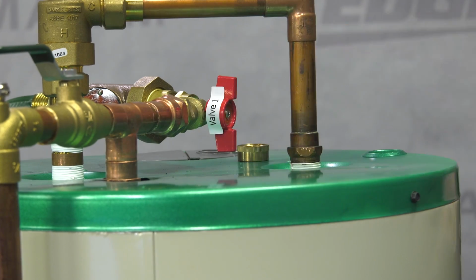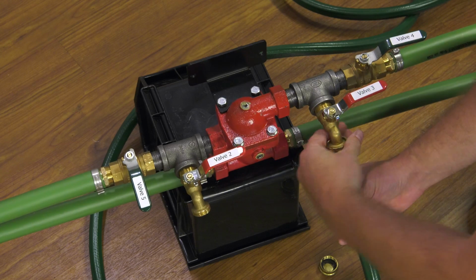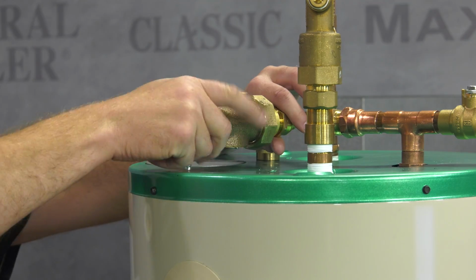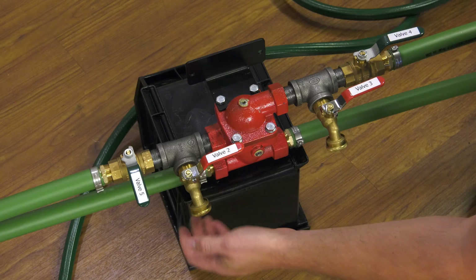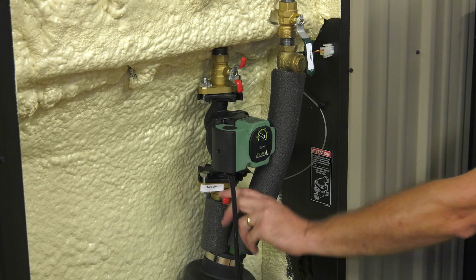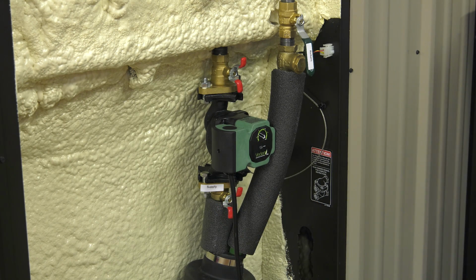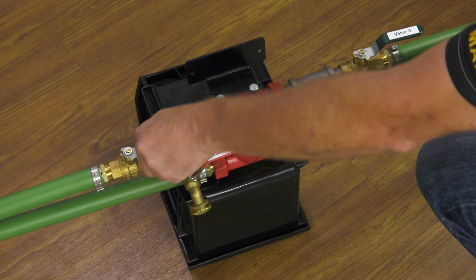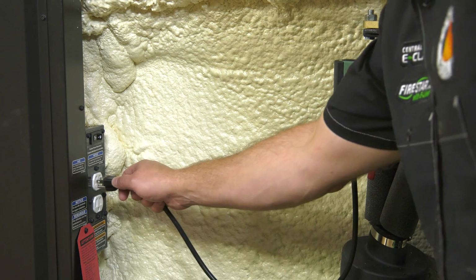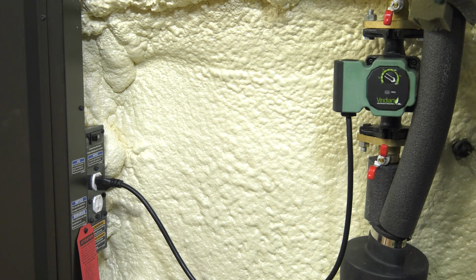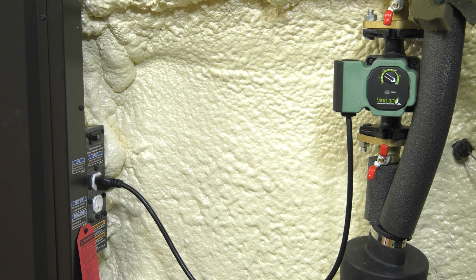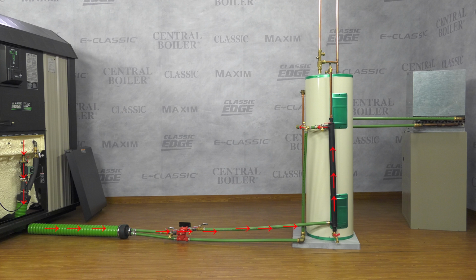Close valves 1 and 3, disconnect the garden hose and the backflow preventer and replace the caps on valves 1, 2, and 3. Open the valve on the hot supply line of the outdoor furnace and valve 5. Start and run the pump or pumps for 24 hours and then perform a water test. At this point, the valves on the hot supply and return lines of the outdoor furnace and valves 4 and 5 should all be open, allowing the pump to circulate heated water in the system.